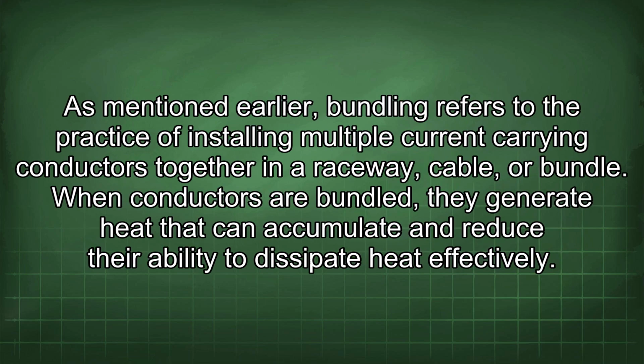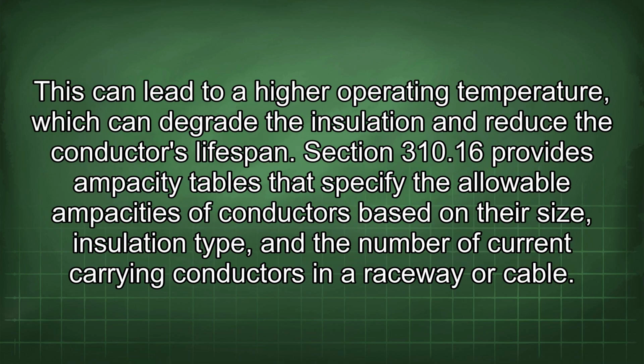As mentioned earlier, bundling refers to the practice of installing multiple current-carrying conductors together in a raceway, cable, or bundle. When conductors are bundled, they generate heat that can accumulate and reduce their ability to dissipate heat effectively. This can lead to a higher operating temperature, which can degrade the insulation and reduce the conductor's lifespan.